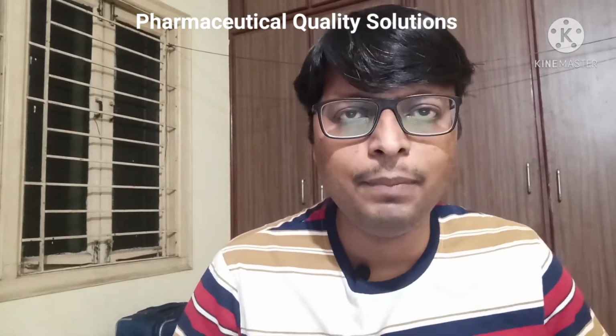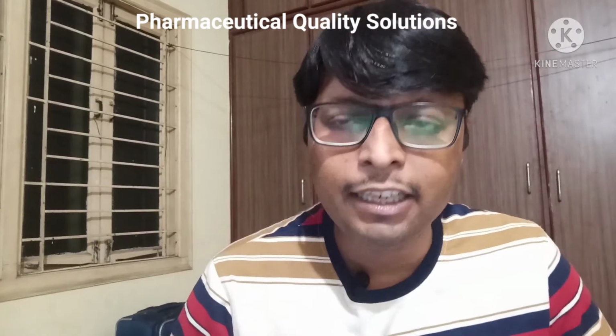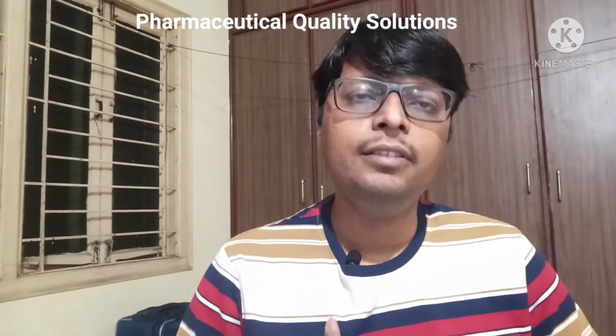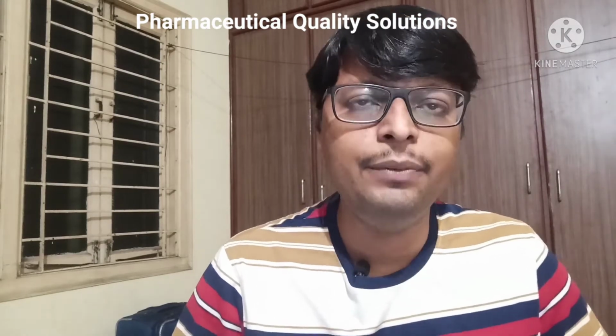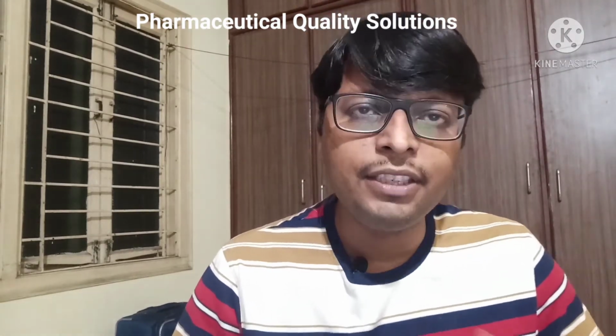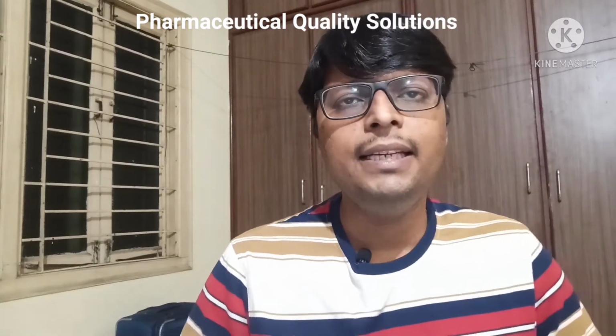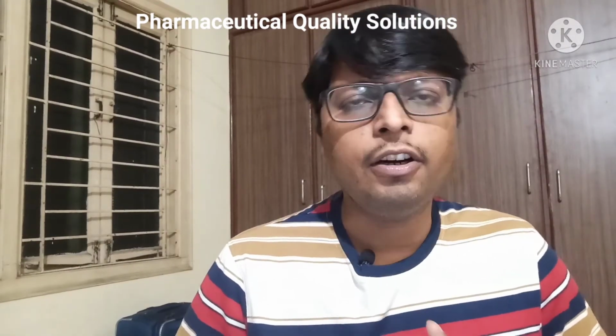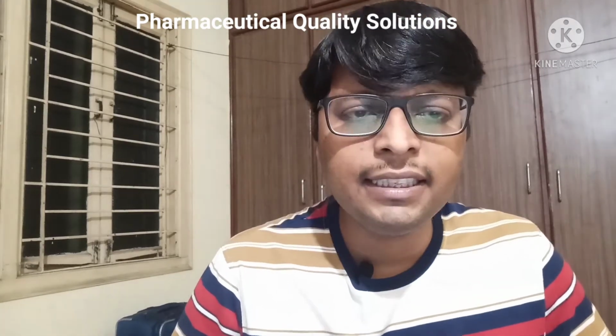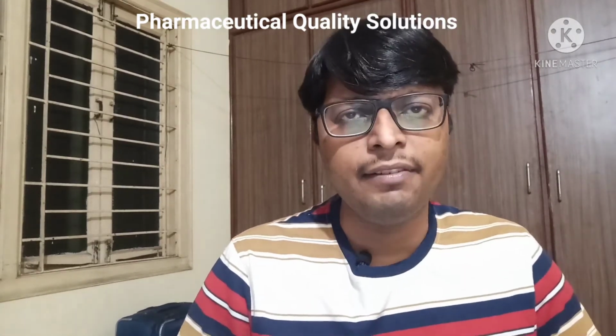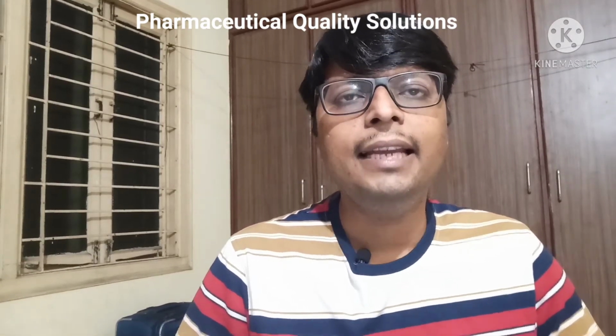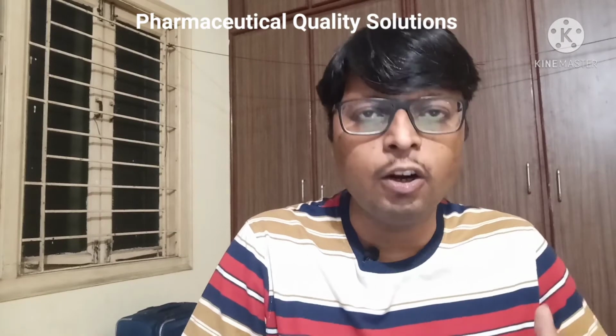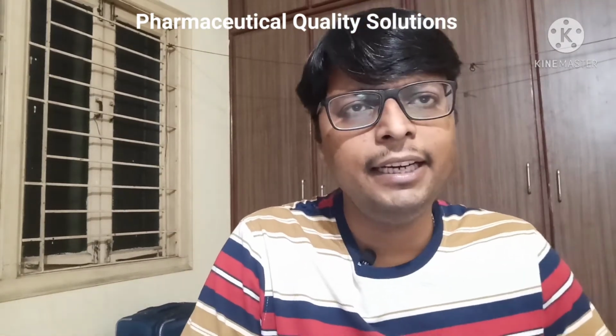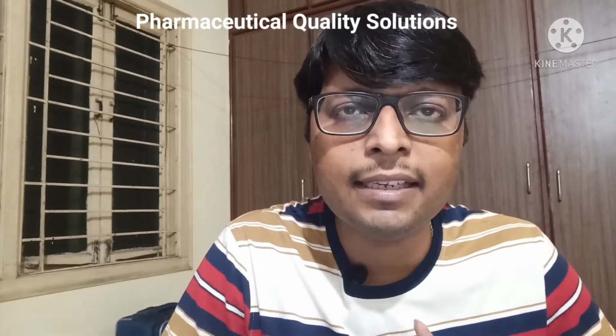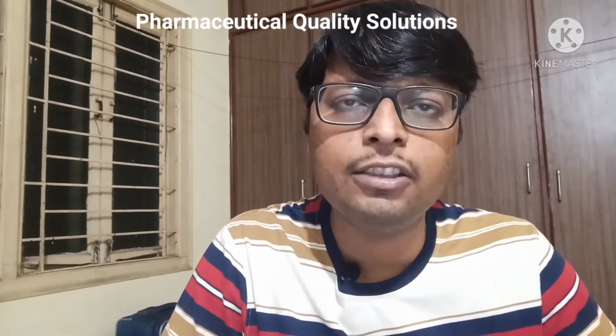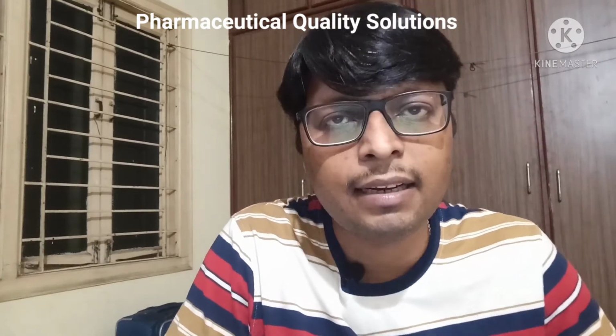There are several categories, so please study all those. Analytical equipment comes under GAMP 3, and it is divided into three categories, GAMP 3A, 3B and 3C. What are GAMP 3 instruments? These instruments or equipment do not require any calibration, and they do not give any measurement values. Guys, understood what I am telling? Take any sonicator or hot plate; these are used as analytical equipment, but they do not give any measurement or result, so no calibration is required. This comes under GAMP 3A.